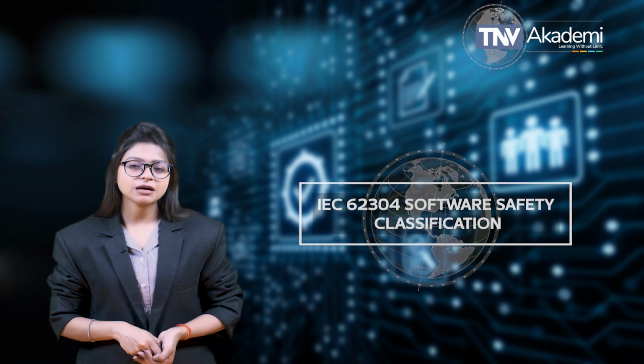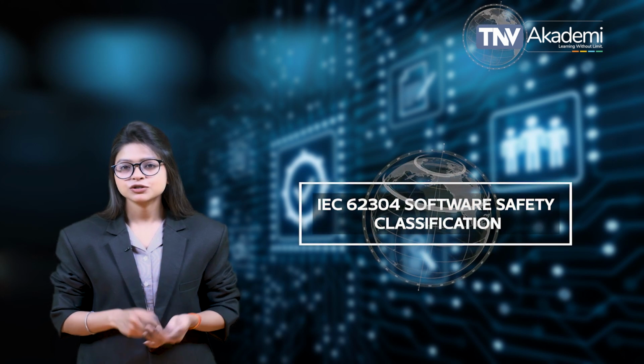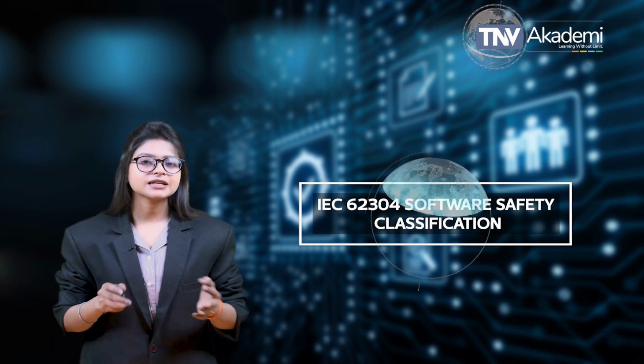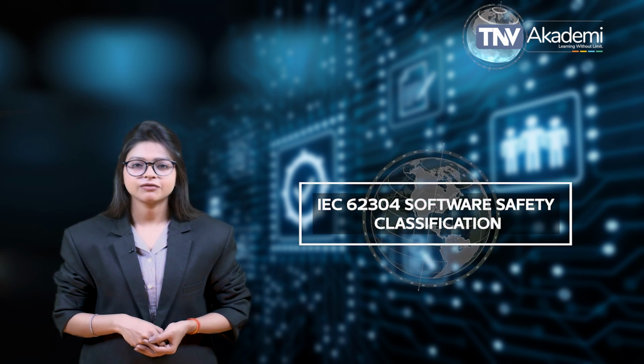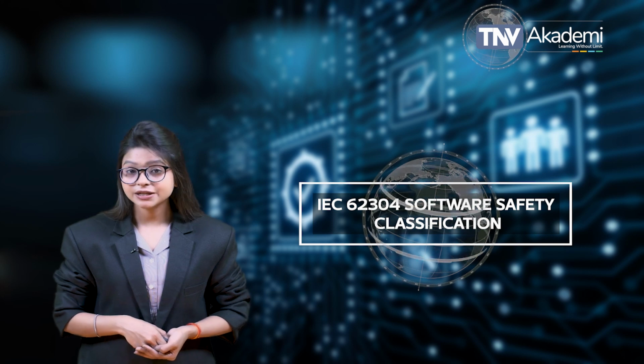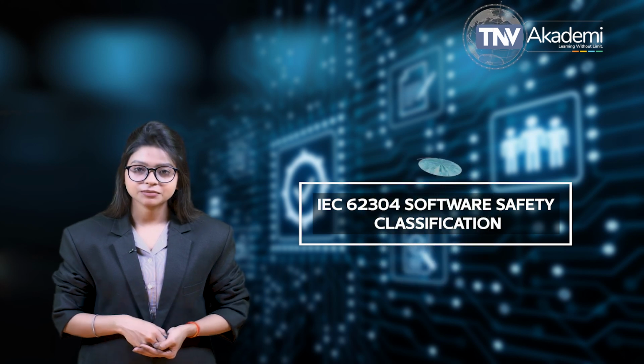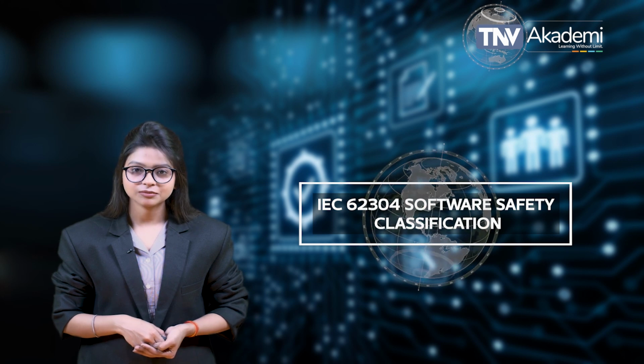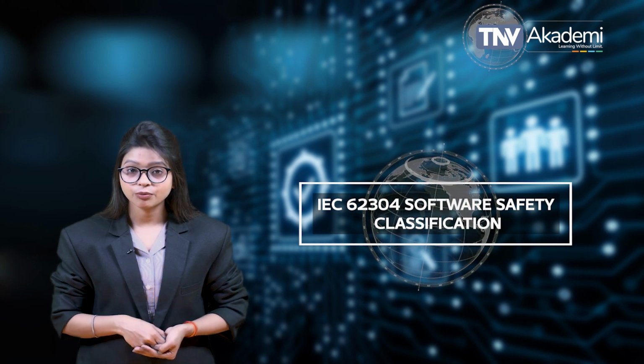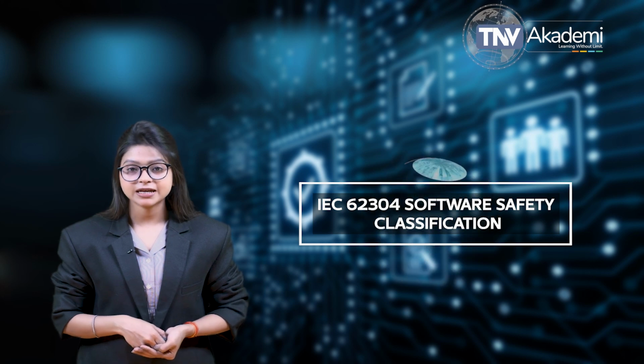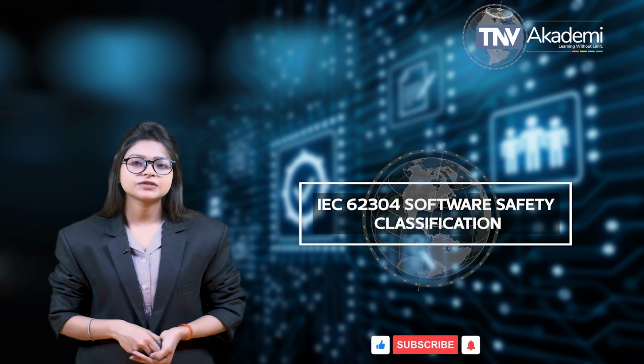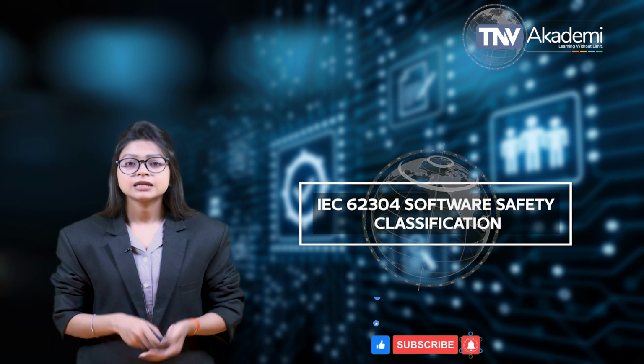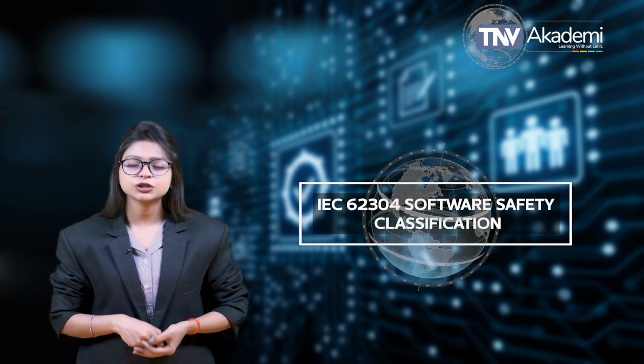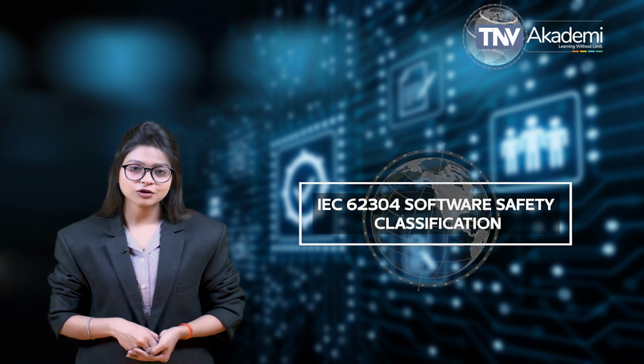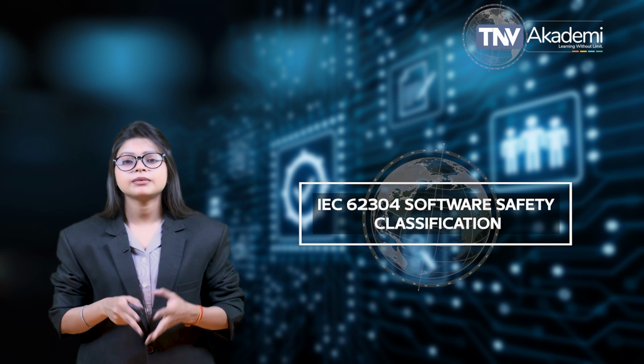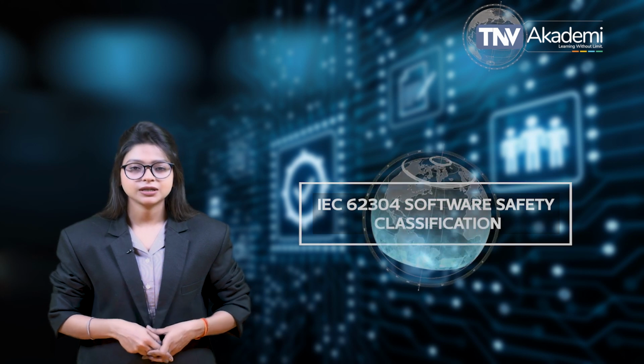So we will now discuss IEC 62304 software safety classification. It's important to ensure safety from the start of development. Product testing isn't enough to ensure patient safety, and patient safety is critical. Plus, building safety into your processes early on saves time and expense later. Software safety classification in the standard determines the safety related processes you will need to use. This impacts the entire software development lifecycle, from requirements and coding to release and maintenance.